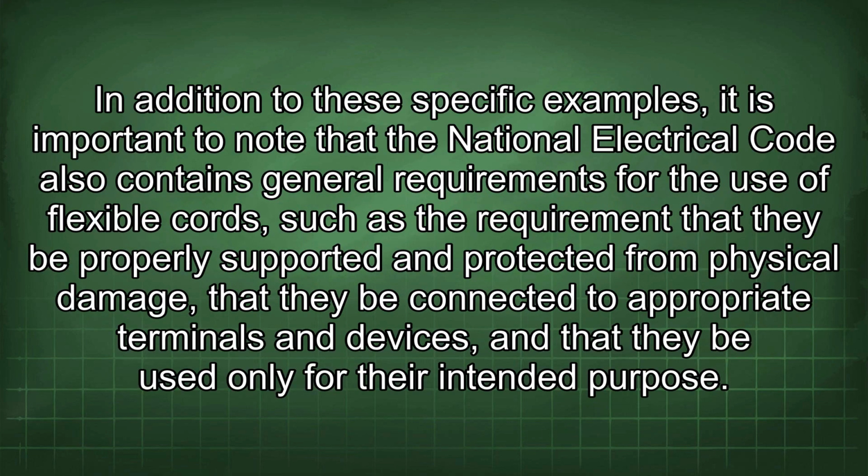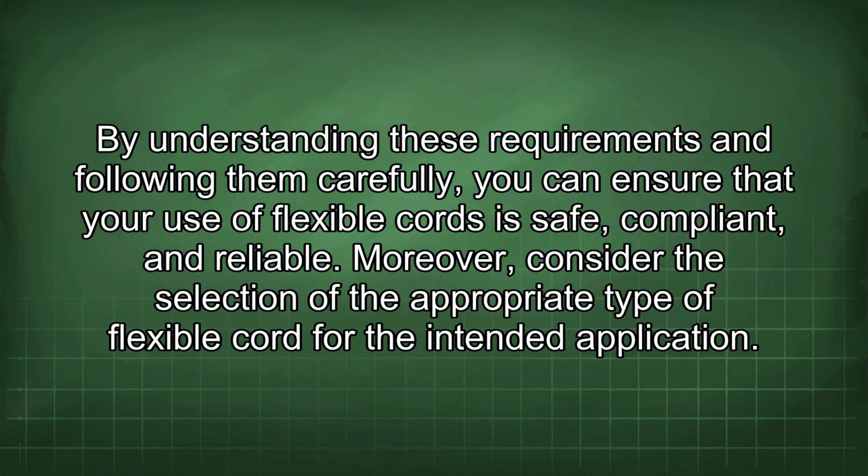In addition to these specific examples, it is important to note that the National Electrical Code also contains general requirements for the use of flexible cords, such as the requirement that they be properly supported and protected from physical damage, that they be connected to appropriate terminals and devices, and that they be used only for their intended purpose.